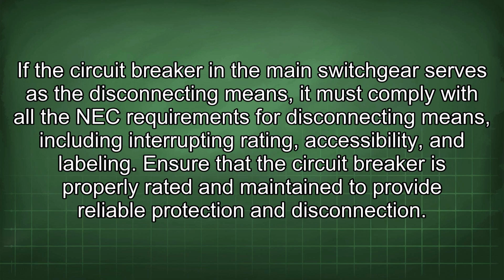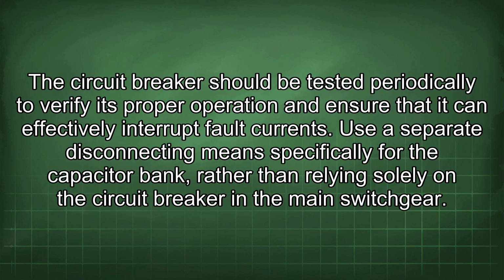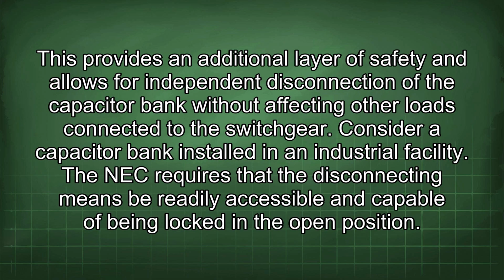If the circuit breaker in the main switchgear serves as the disconnecting means, it must comply with all the NEC requirements for disconnecting means, including interrupting rating, accessibility, and labeling. Ensure that the circuit breaker is properly rated and maintained to provide reliable protection and disconnection. The circuit breaker should be tested periodically to verify its proper operation and ensure that it can effectively interrupt fault currents. Use a separate disconnecting means specifically for the capacitor bank, rather than relying solely on the circuit breaker in the main switchgear. This provides an additional layer of safety and allows for independent disconnection of the capacitor bank without affecting other loads connected to the switchgear.